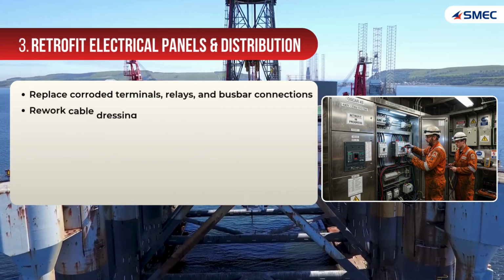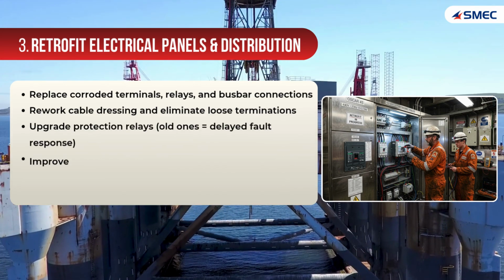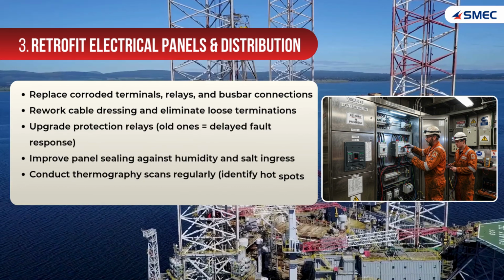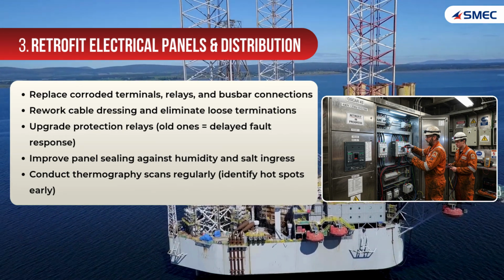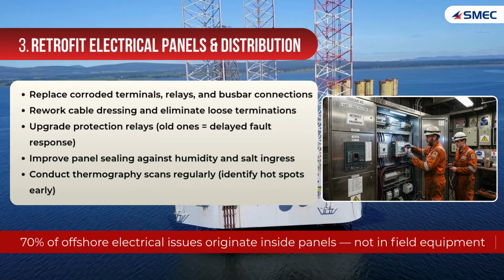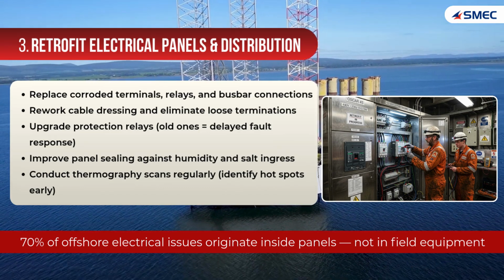70% of offshore electrical issues start inside the panel. Replace the corroded terminals and old protection relays. Their delayed response time is a liability. Improve sealing against salt ingress and use thermography to kill hotspots before they start fires.